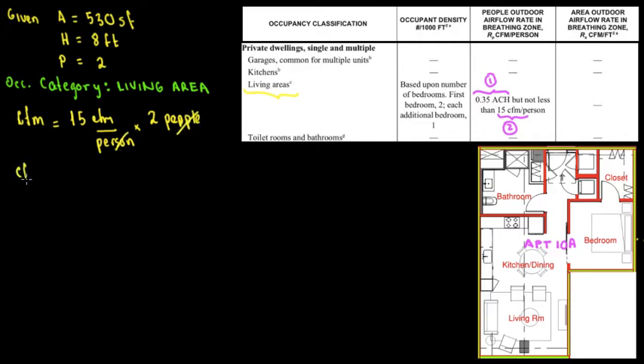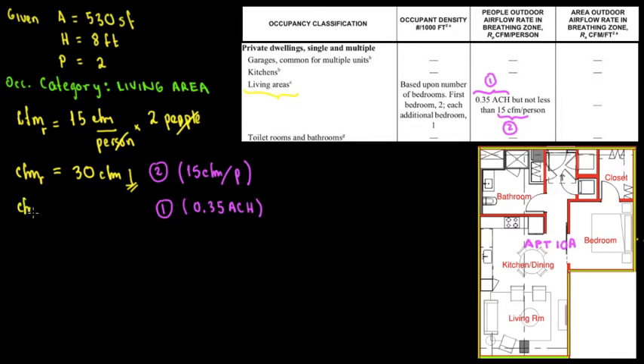So the CFM required is going to be 15 times 2, that's going to be 30 CFM. So we need 30 CFM in this case. But that's option 2, number 2, which indicates this has to be no less than 15 CFM per person. But in the previous video, we utilized 0.35 air changes per hour, and the CFM required was 24.73 CFM. That was in part 1.